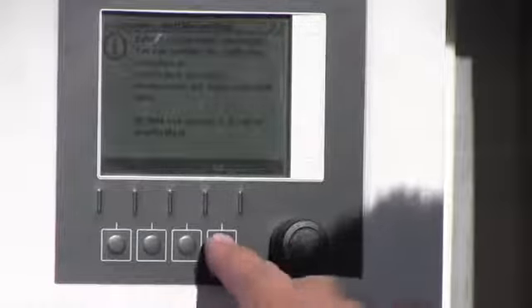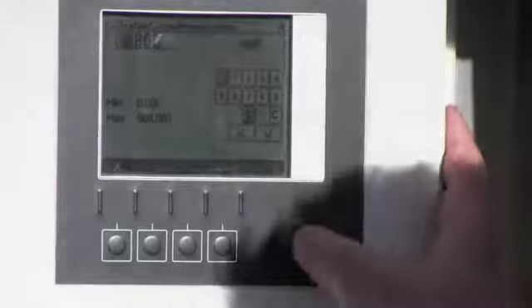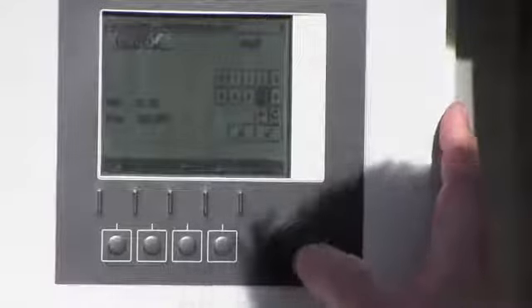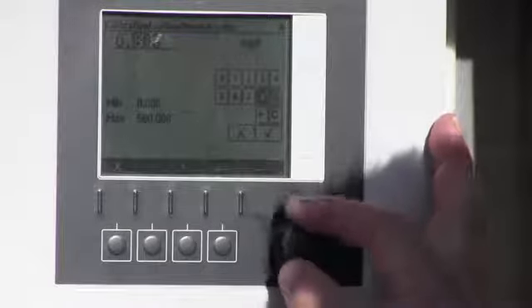Hold was activated. We're going to select OK. It says continue calibration. We hit enter. And this line here is highlighted of the residual value that the unit's reading. We want to select the jog shuttle button and hit enter. And we now have a table for data entry of our calibration value. Our DPD test resulted in the same reading here of a 0.86. I simply hit the 0 highlighted. I hit the jog shuttle button. It jumps to the decimal. I hit it again. Now I can change the value here by rotating the jog shuttle button.